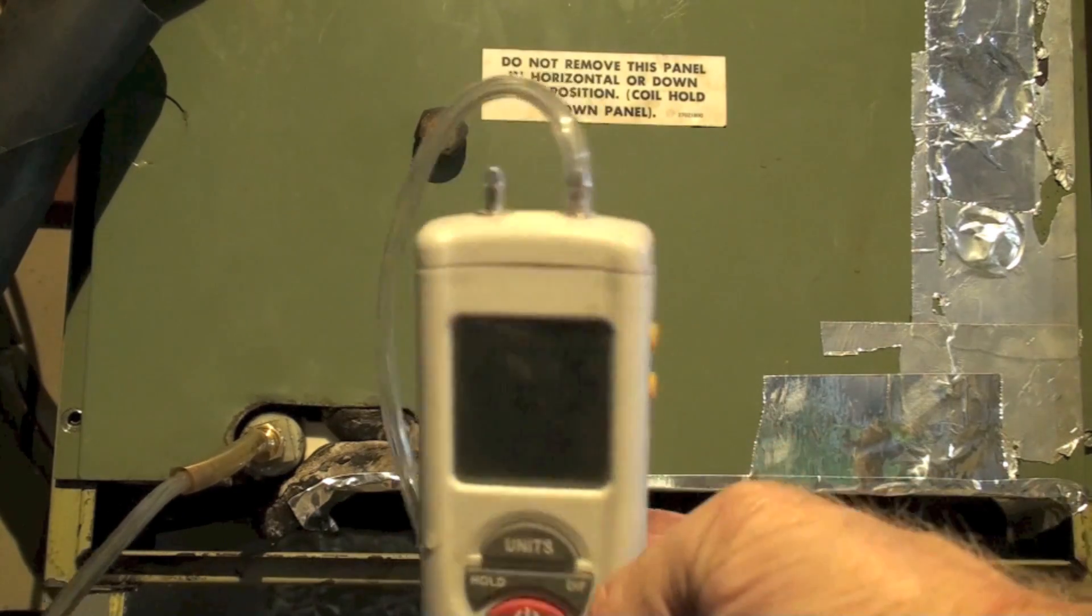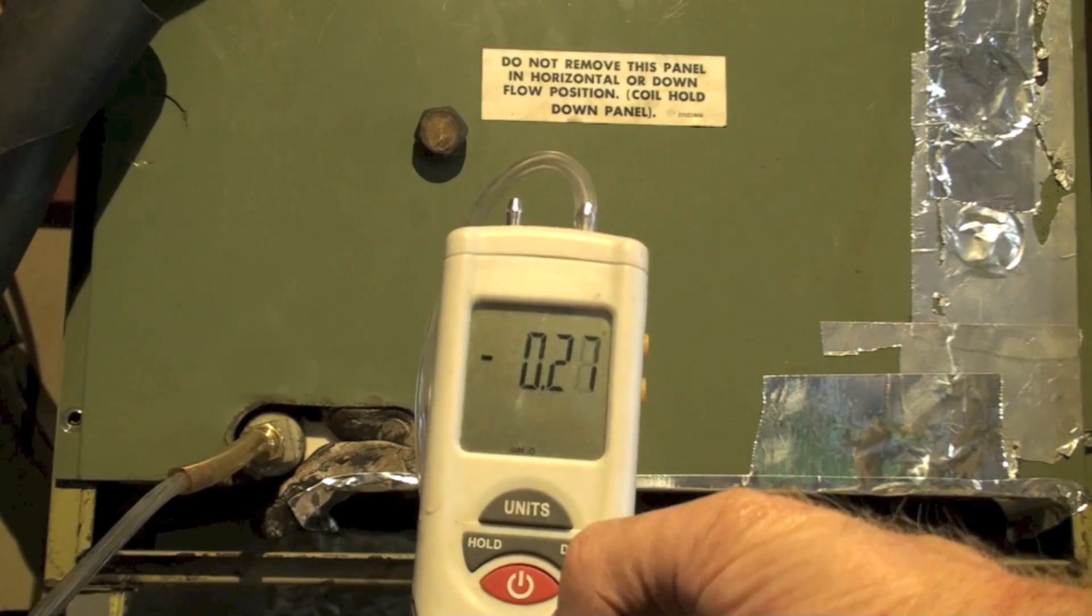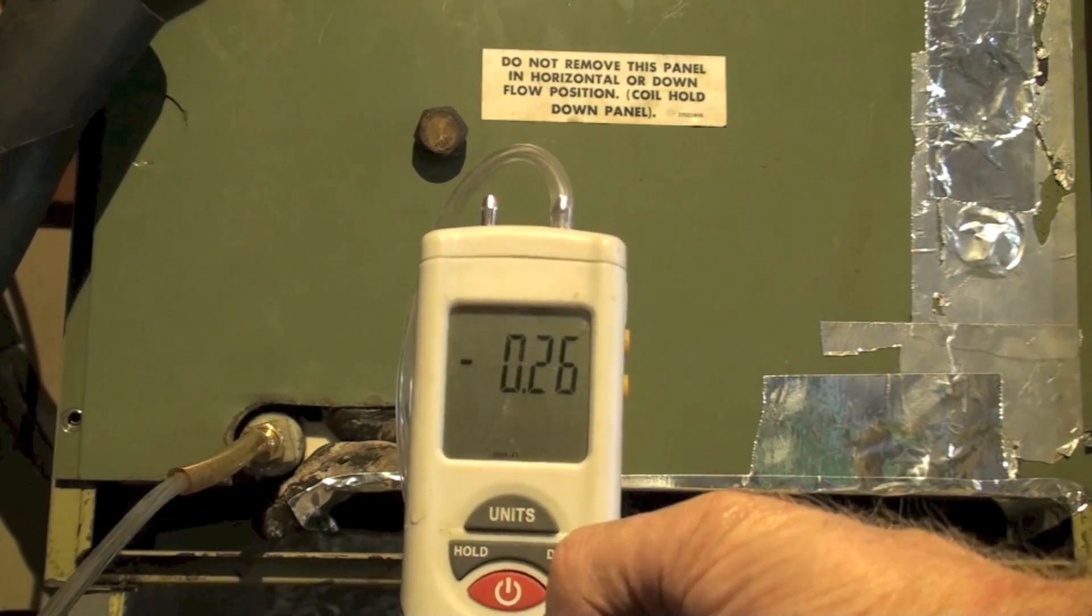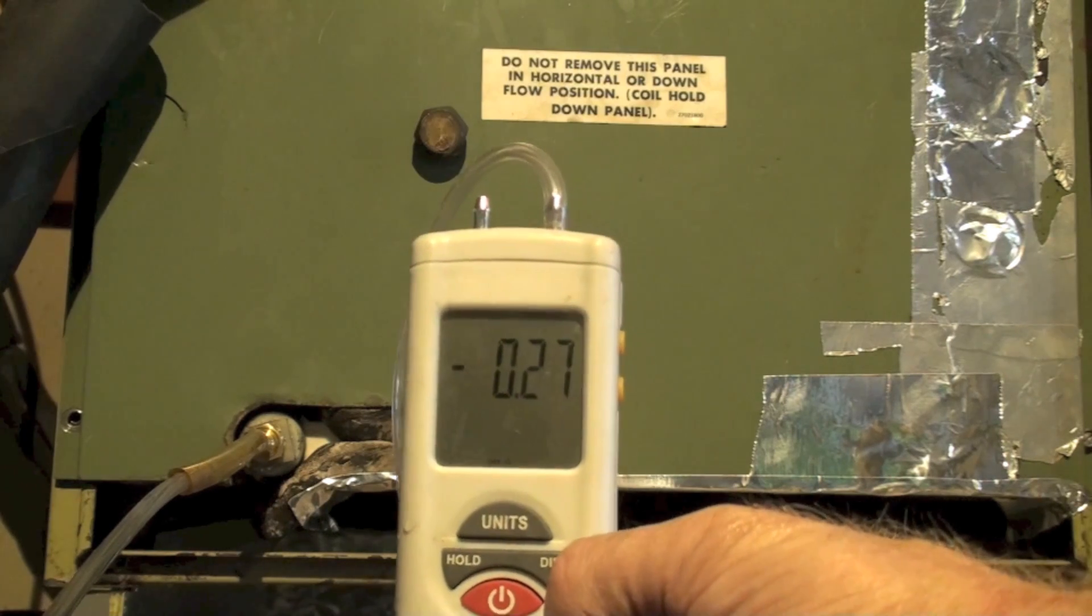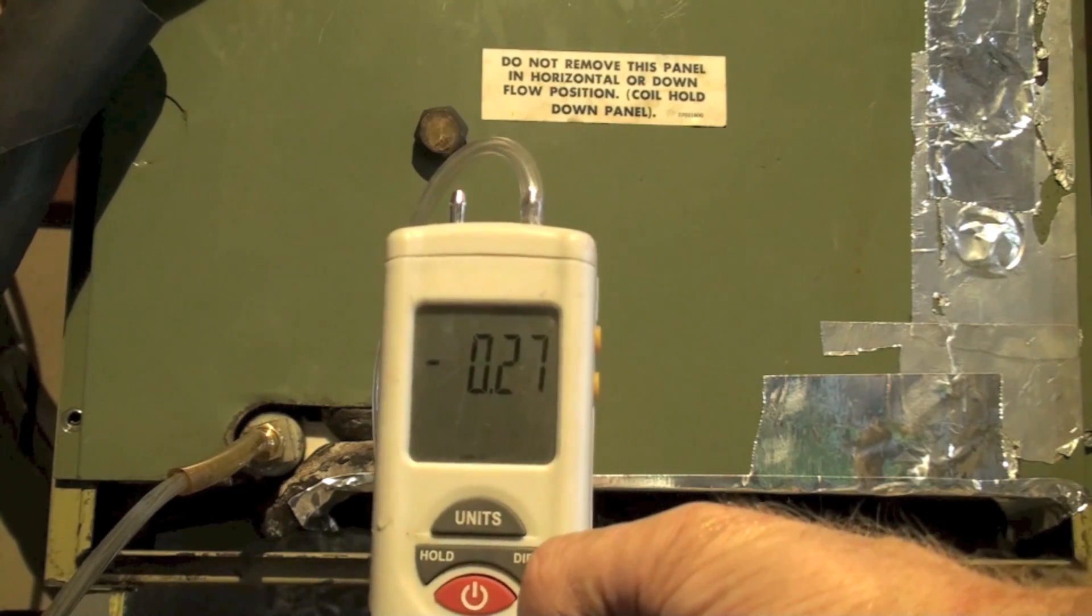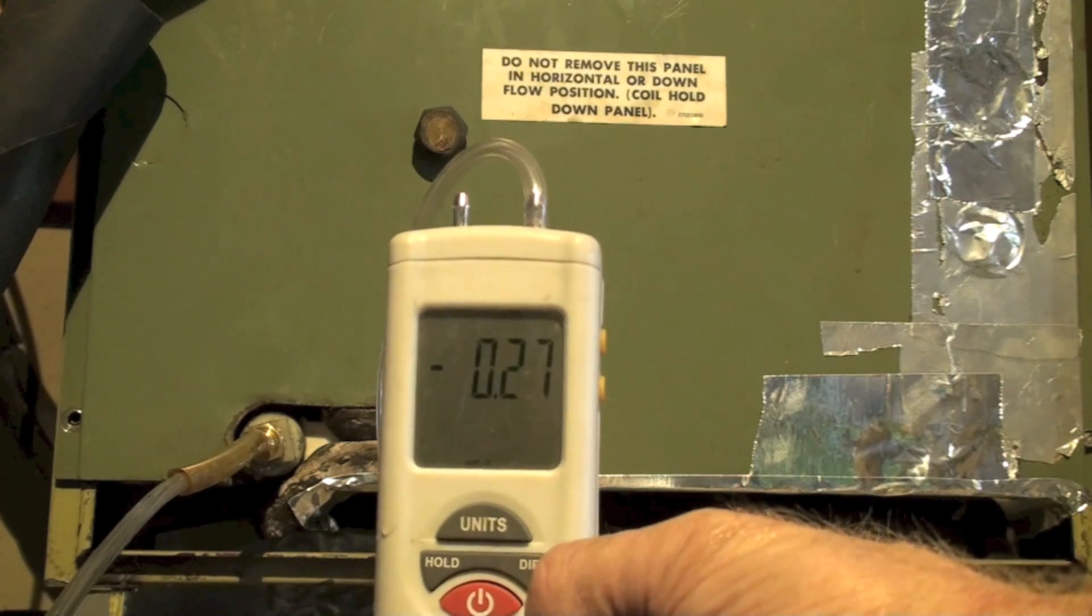I've got a manometer hooked up to this thing. You can see we've got a negative pressure of about 0.27 to 0.26 water column. So that's enough that it's going to suck air back in.